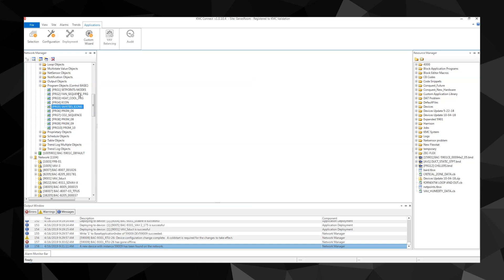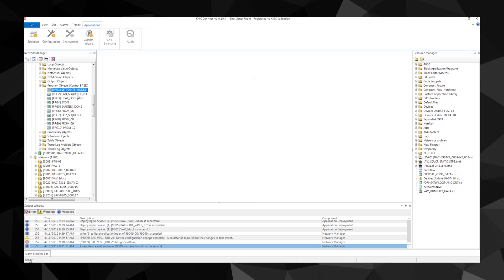The first program is generally always setpoints and modes. The data and calculations in this program drive all the other decisions and logic in the control sequence. Once the setpoint and mode program is complete, the fan program is run. Programming logic decides what state the fan should run based on the variable references and calculations from the previous program.